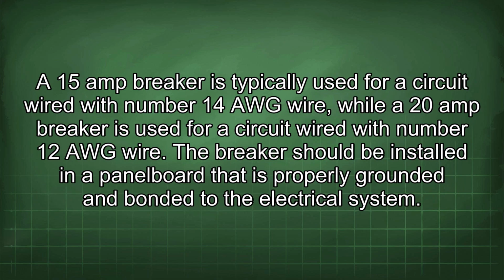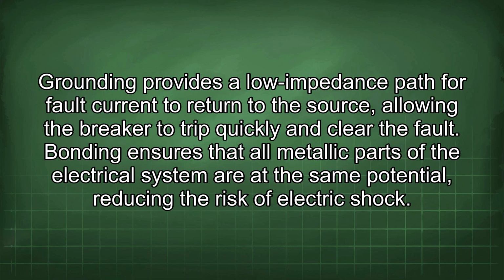A 15 amp breaker is typically used for a circuit wired with number 14 AWG wire, while a 20 amp breaker is used for a circuit wired with number 12 AWG wire. The breaker should be installed in a panel board that is properly grounded and bonded to the electrical system. Grounding provides a low impedance path for fault current to return to the source, allowing the breaker to trip quickly and clear the fault. Bonding ensures that all metallic parts of the electrical system are at the same potential, reducing the risk of electric shock.